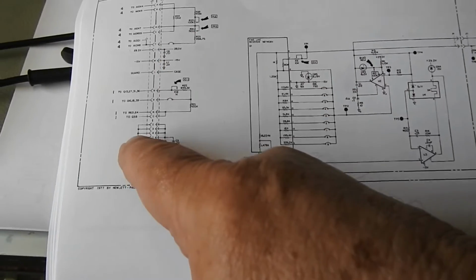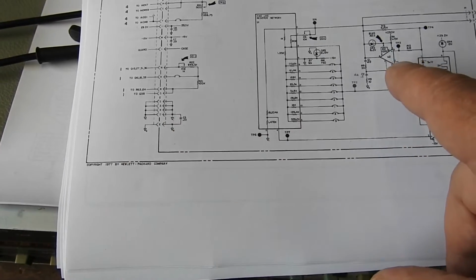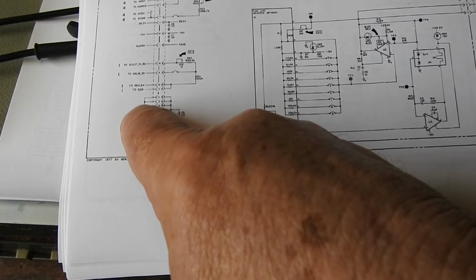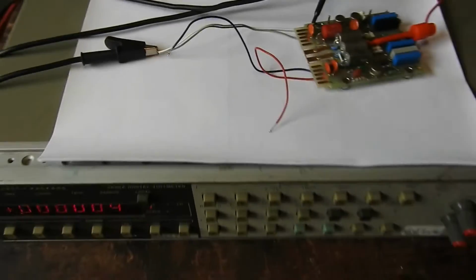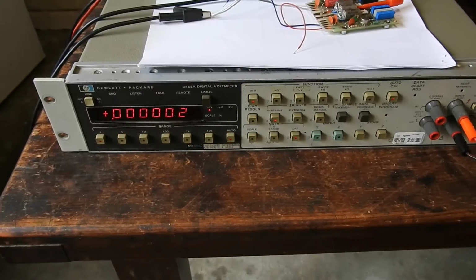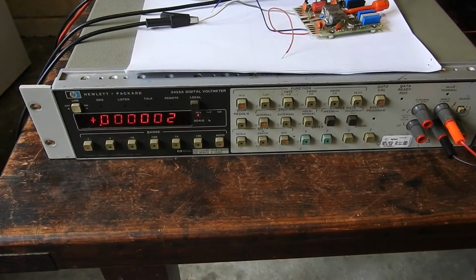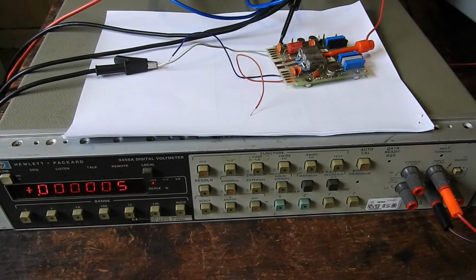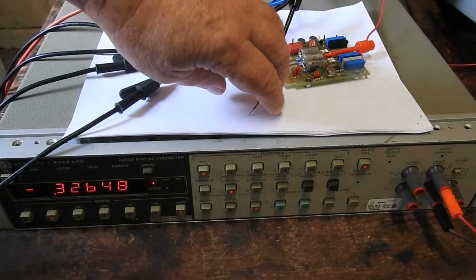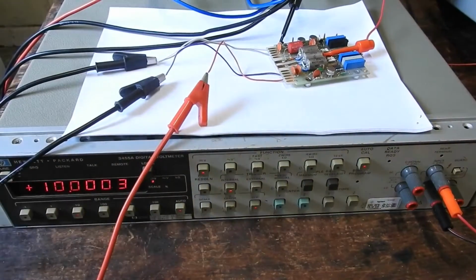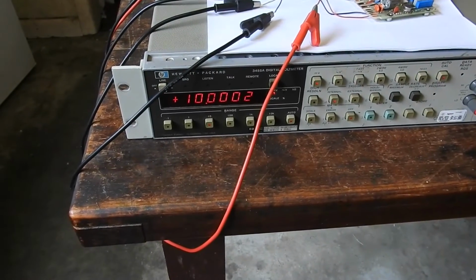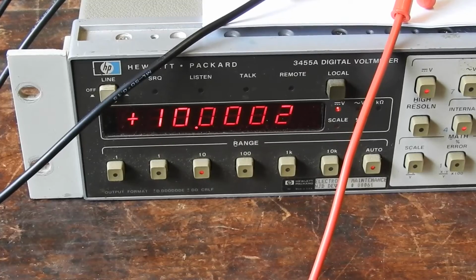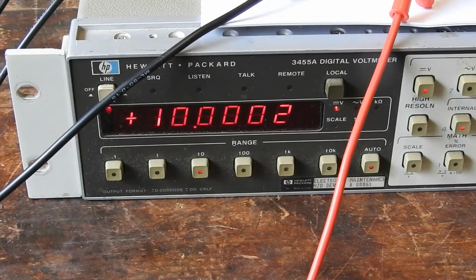hard to replace. So we need plus 29.3 volts for the heater, uses -15, so there and there, and grounds are here. There's also another ground which this appears to use, ground R, so I'll connect those 2 grounds together, which is those 2, and we're looking at the output voltage on the good HP3455, and connect the -15 first, and then the heater power, and we get 3.2 something, and look at that, 10 point not much, so I guess that's a relief. The reference works, so there's something on the motherboard that's screwing up the reference voltages, and it can't be much.